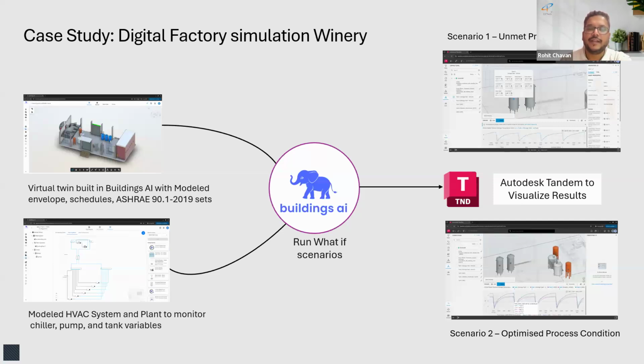So we created multiple scenarios for what needed to change so process conditions could be met. We found different issues - instead of immediately upgrading the chillers, we suggested multiple changes in the HVAC systems, like adding particular insulation to the fermentation tank and changing a few chiller parameters. With zero capex increase, we were able to play out these scenarios digitally in our Buildings AI platform, and once everything was under control, the process conditions were met - because to get the perfect wine, the fermentation tank needs to be at less than 4 degrees Celsius.